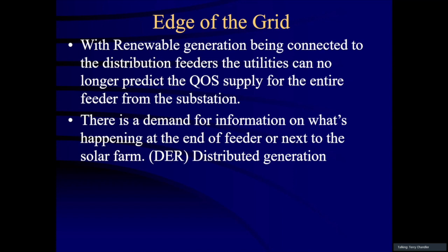The challenge, as I talked a little bit about with renewable generation, is when people want to put a photovoltaic system on the roof of their factory or in their backyard and connect it to the utility, you're going to connect to the distribution system, not to the transmission system. Prior to this, all power was generated in power plants and transferred to the transmission system, then to the distribution system, and then to the customer. Now the customer is going to be generating and feeding it back into the system in what we call reverse power flow. That's a big challenge for the utilities for all kinds of reasons, but they still have to maintain the voltage on all that same feeder.